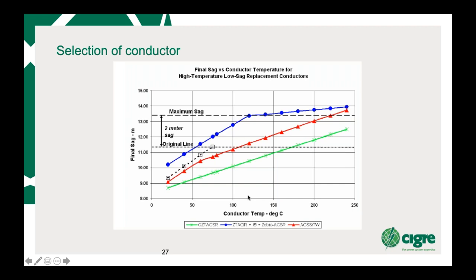Looking at the ACSS/TW, it has a low knee point, and this is due to the fact that the strands are all annealed and very, very soft. So all the load goes onto the steel core, which enables you to have a low knee point, which then gives you, at 200 degrees C, the ability to reach 200 without reaching a maximum sag. Alternatively, if you want a really low knee point, you can use a GZTAC, which is this green line, which has no knee point, and that goes purely on the steel core. So this is a steel core curve here, and you can get it well within the sag requirements.